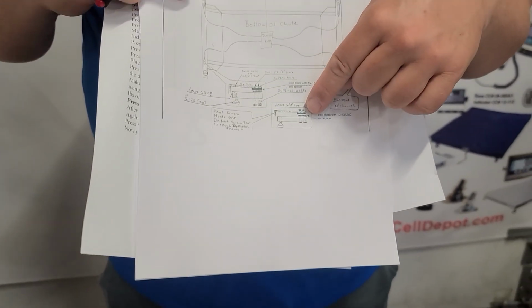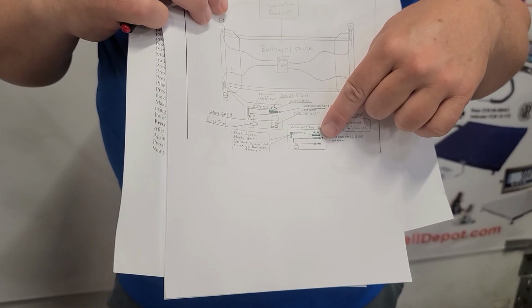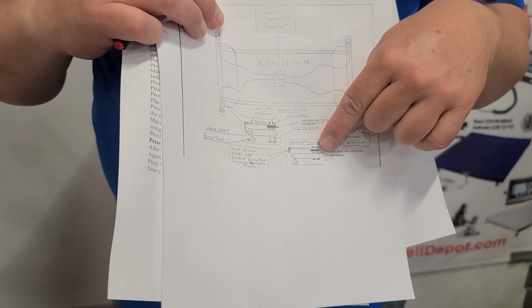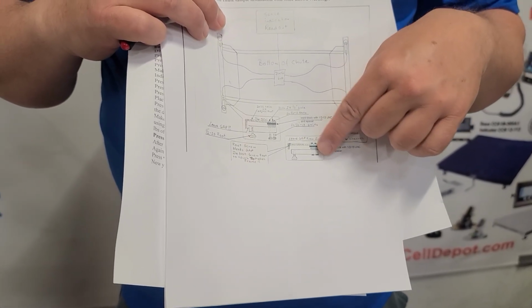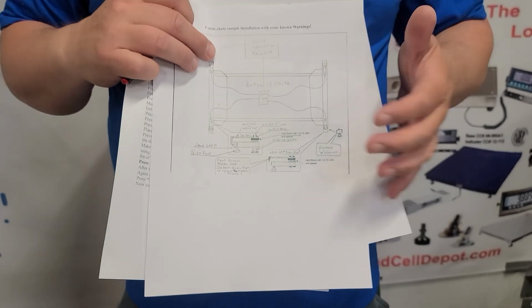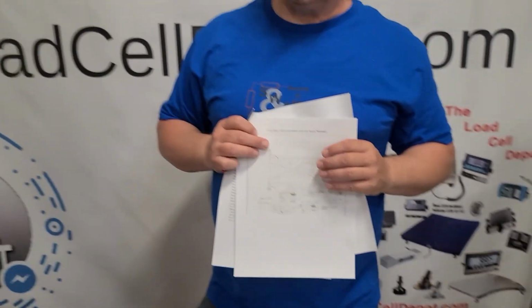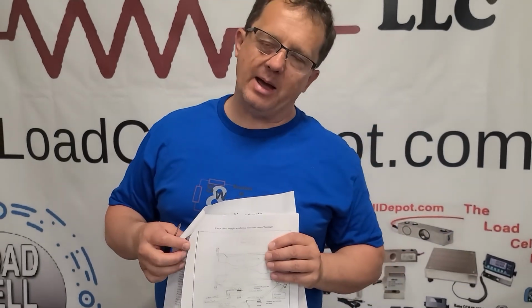As you see, the plate, the shim plate, and the threaded block sit right between your load cell. You don't really have to use the shim plate, but if your scale has a lot of gaps and isn't level correctly, you can stack up some shims on one side and put less on the other side.